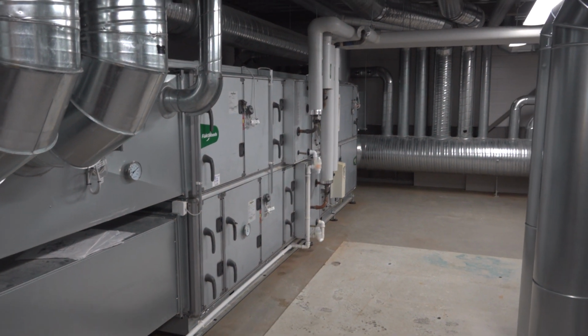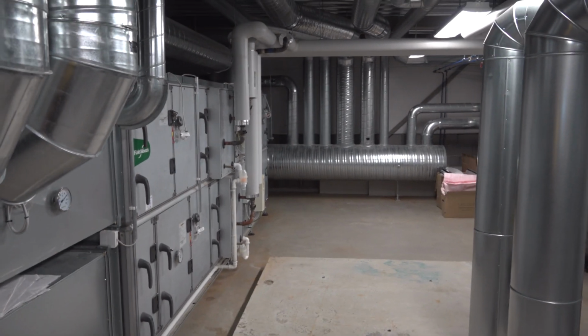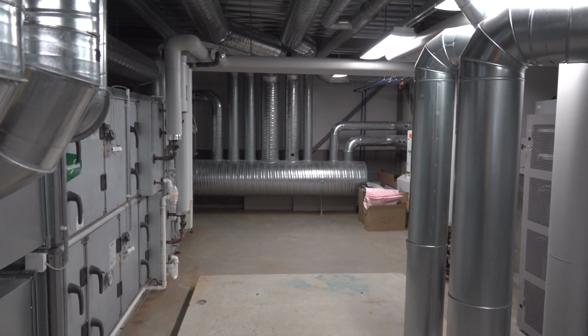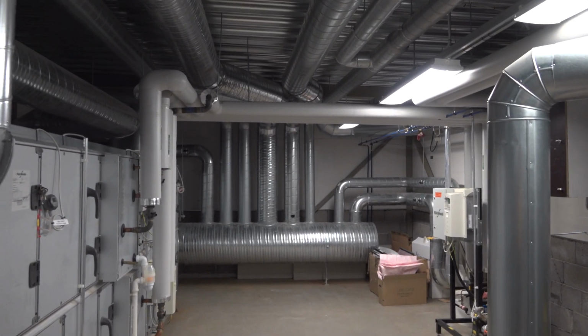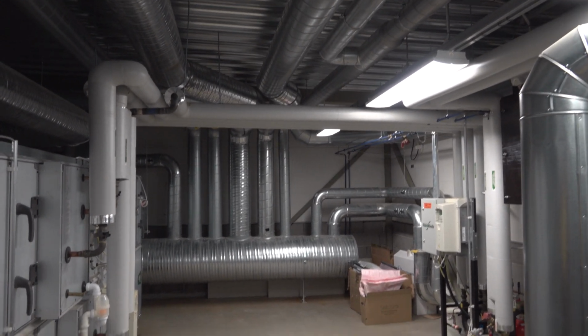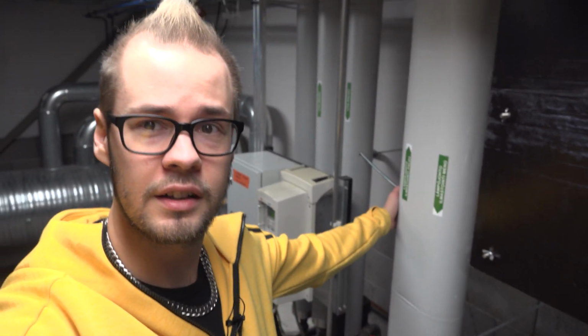Everything here is monitored by the computer, and if there are values that are off, it sends an automatic notification to the service company via text message. But yeah, there's the heat exchangers and the heat exchanger circuit. Let's go check on the basement where these tubes go and where we get the district heating energy.